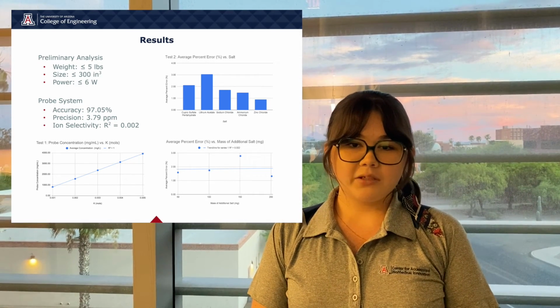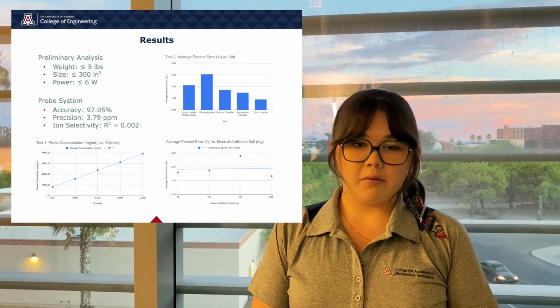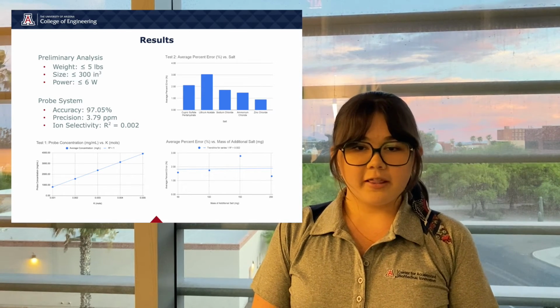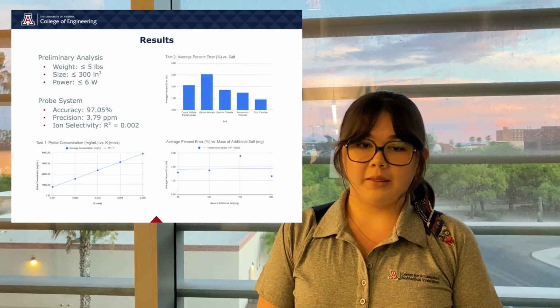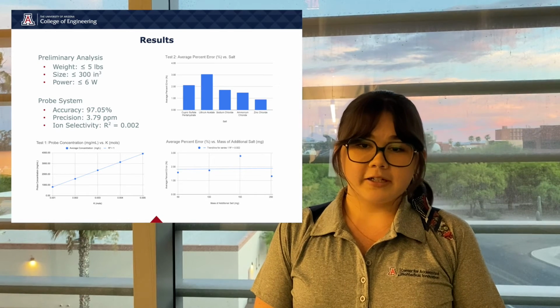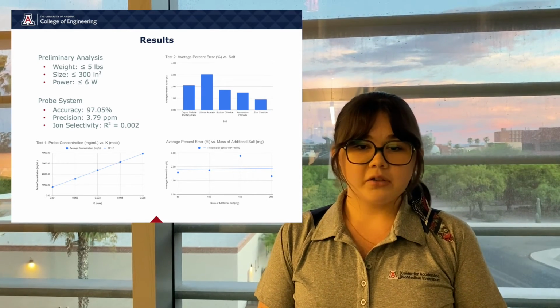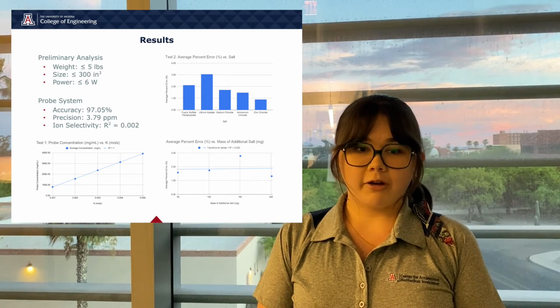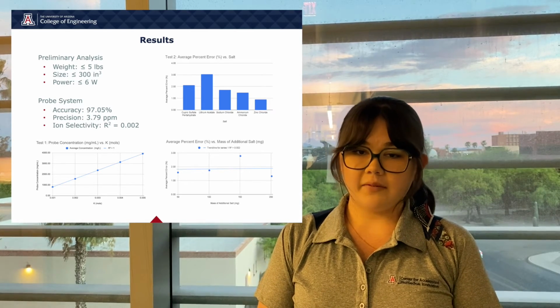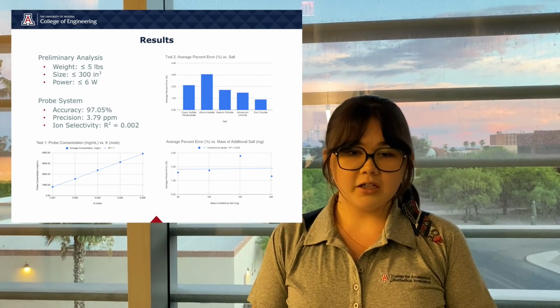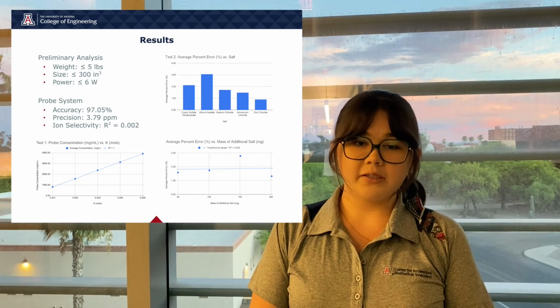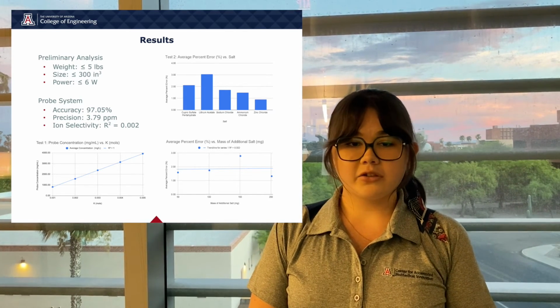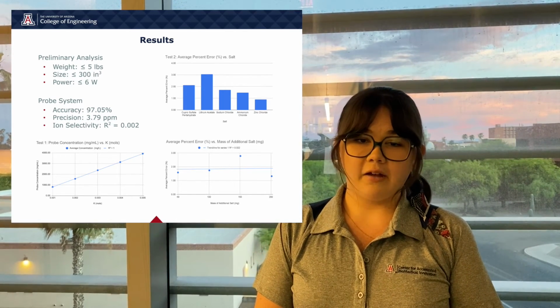During our second test, we looked at the ion selectivity of the probe system. This is to ensure that other ions do not interfere with the accuracy of our probe. During this test, we added various salts to a known potassium solution. When graphing percent error versus mass of the additional salt, we determined that the R-squared is 0.002, meaning that other salts do not interfere with the accuracy of our probe system.